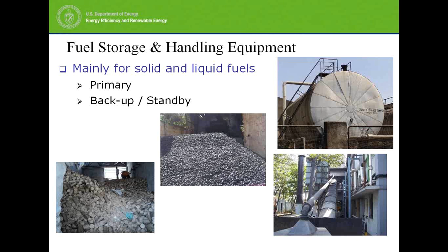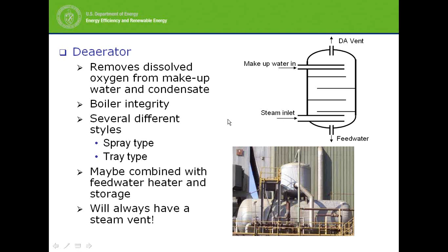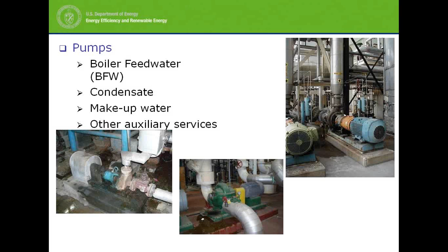Once we get to the steam side, you've got the deaerator. We'll talk a lot about it in the class for sure. We'll evaluate some of the reasons why it's there. But the main purpose of it is to remove the dissolved oxygen from the makeup water and condensate and heat the water at the same time. Generally, we'll have a steam vent to remove all the dissolved oxygen and the other inert gases. Pumps are something that will take the water, which is now feed water, out of the deaerator, so the boiler feed water pump comes in. There are several additional pumps in a steam system: condensate pumps, makeup water pumps, other auxiliary services, dosing pumps for chemical input, and so on and so forth.